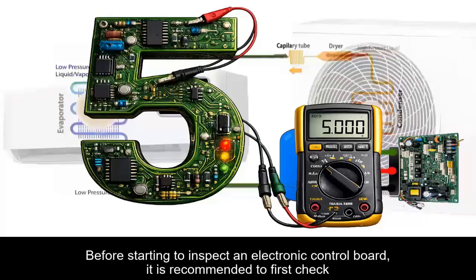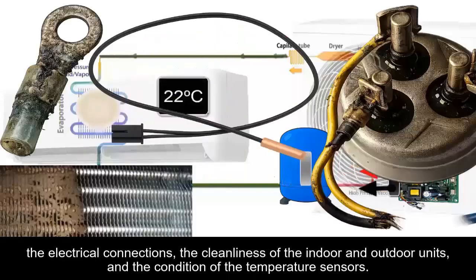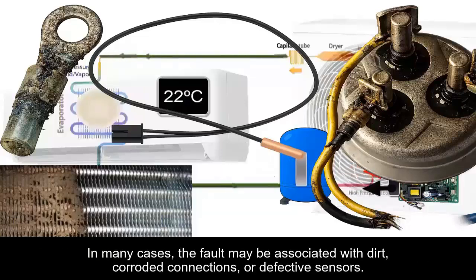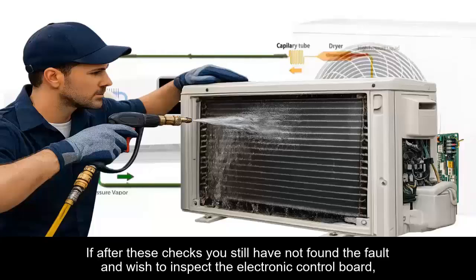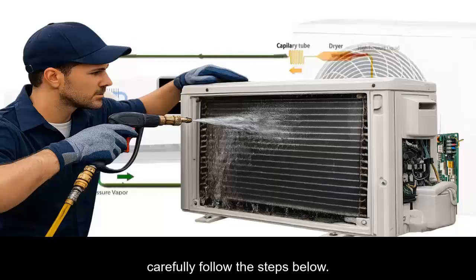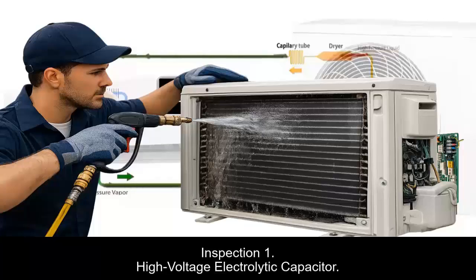Before starting to inspect an electronic control board, it is recommended to first check the electrical connections, the cleanliness of the indoor and outdoor units, and the condition of the temperature sensors. In many cases, the fault may be associated with dirt, corroded connections, or defective sensors. If after these checks you still have not found the fault and wish to inspect the electronic control board, carefully follow the steps below.